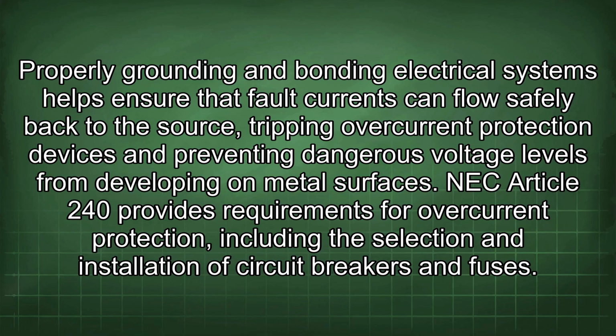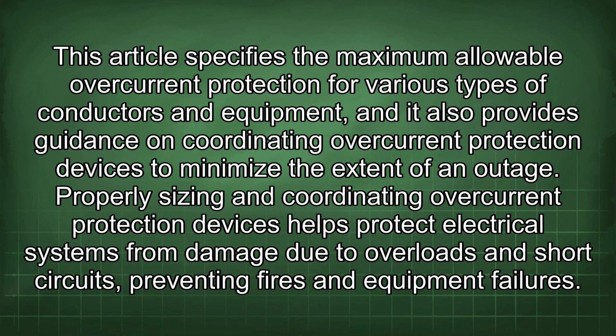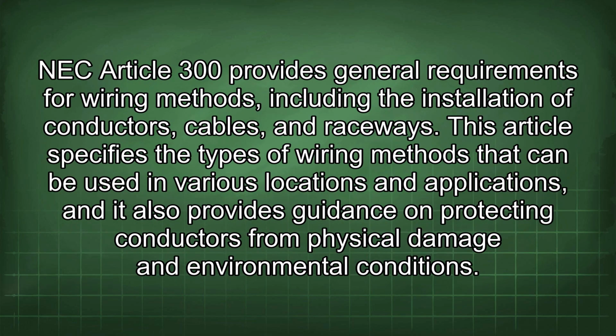NEC Article 240 provides requirements for overcurrent protection, including the selection and installation of circuit breakers and fuses. This article specifies the maximum allowable overcurrent protection for various types of conductors and equipment, and it also provides guidance on coordinating overcurrent protection devices to minimize the extent of an outage. Properly sizing and coordinating overcurrent protection devices helps protect electrical systems from damage due to overloads and short circuits, preventing fires and equipment failures. NEC Article 300 provides general requirements for wiring methods, including the installation of conductors, cables, and raceways.